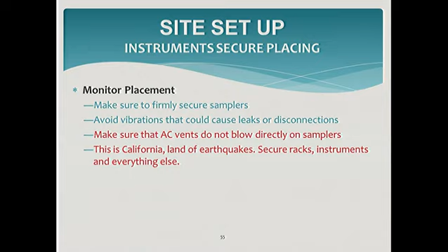Just please note that the recommendation about avoiding air conditioner vents blowing directly into the inlets or the instruments is critical, because that could lead to performance issues. So in some cases, the samplers could be tracking the changes in temperatures inside the room during normal sampling conditions, or during nightly calibration checks. And I'm not sure if you guys have seen that problem, but it's quite frequent that it happens.